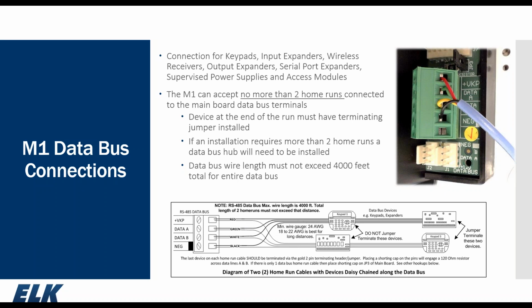We may ask you, well, let's check the resistance. 60 to 70 is good. If it's more than 120, you're missing a jumper. If it's less than 40, you may have one too many jumpers, which could be a problem as well. So it's just a matter of making sure that we get the data bus configured correctly.